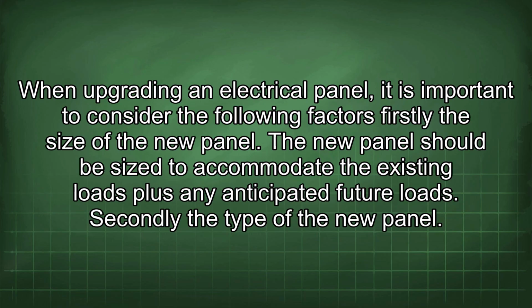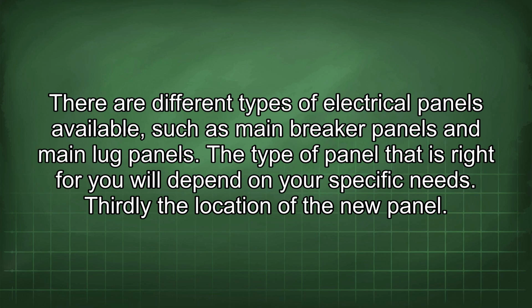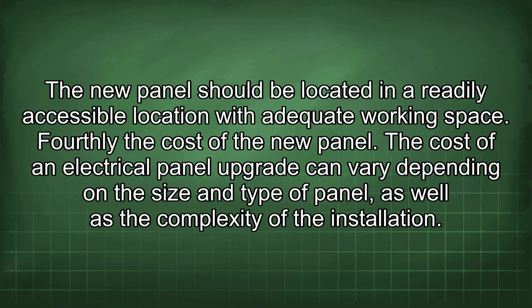When upgrading an electrical panel, it is important to consider the following factors. Firstly, the size of the new panel. The new panel should be sized to accommodate the existing loads plus any anticipated future loads. Secondly, the type of the new panel. There are different types of electrical panels available, such as main breaker panels and main lug panels. The type of panel that is right for you will depend on your specific needs. Thirdly, the location of the new panel. The new panel should be located in a readily accessible location with adequate working space. Fourthly, the cost of the new panel. The cost of an electrical panel upgrade can vary depending on the size and type of panel, as well as the complexity of the installation.